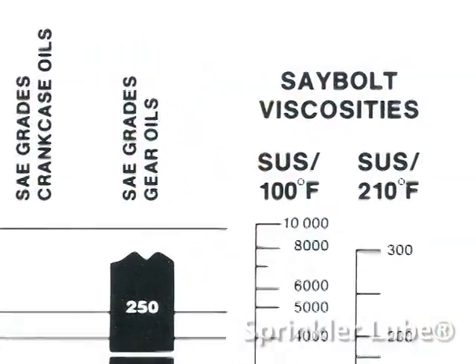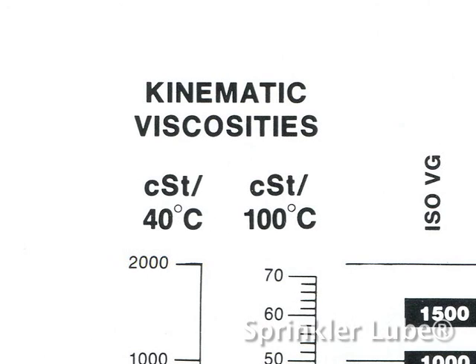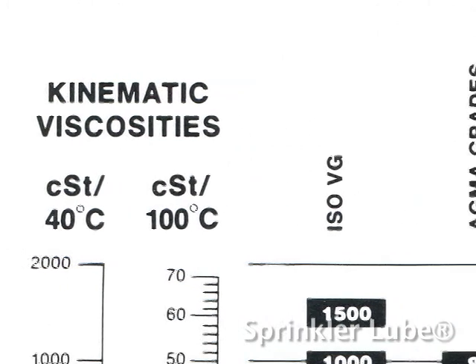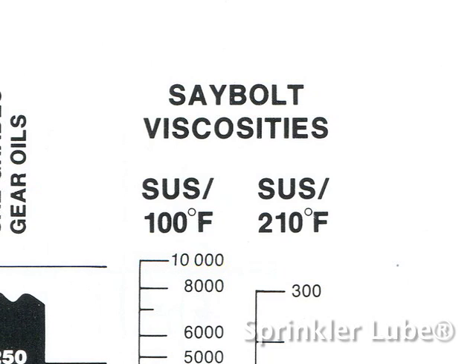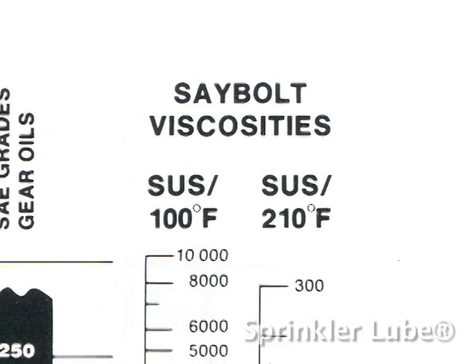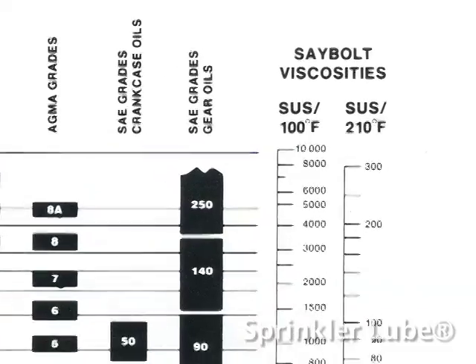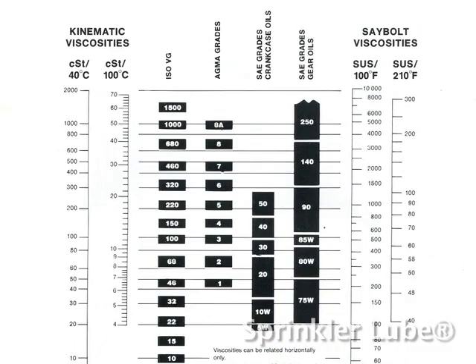It is good practice to look at the tech data sheet and see if the typical specifications show an ISO number or AGMA number. Sometimes you may have a specification sheet for a piece of equipment where the manufacturer uses a number with SSU, SUS, or even CST. If you look at either side of this chart, you will find those numbers at a given temperature. With CST, the temperatures will be at 40°C or 100°C. With SSU or SUS — which actually mean the same thing — temperatures will be at 100°F or 210°F. Once you find the numbers the equipment specification sheet is asking for, you can then cross-reference them to any of these other classification systems.